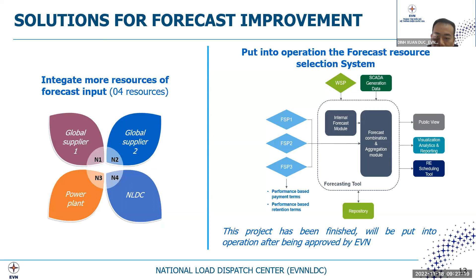The other enhancement to reduce forecasting error relies on the AGC, the automatic generation control. We put the final forecasting result into the AGC, and based on the forecasting of each individual power plant, the AGC sends set point control signals to each power plant to make sure we don't exceed the threshold of the transmission capacity limit.